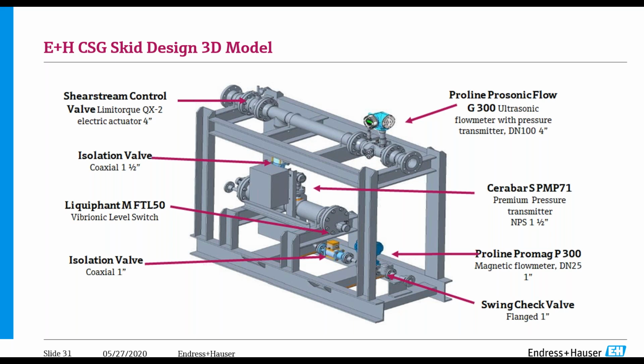We also have the integral temperature and pressure measurement on the flow meter itself, meaning that we can do corrected volume on board the flow meter as opposed to doing it maybe inside an RTU on a control system. And it's there as an option if we want to do that. So that is key for us on our coal seam gas skid design, the G300 flow measurement point. And one of the important outcomes that we wanted to achieve on our design was an accurate and reliable gas flow measurement.